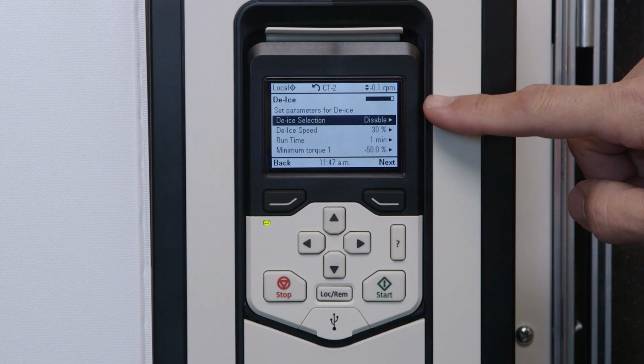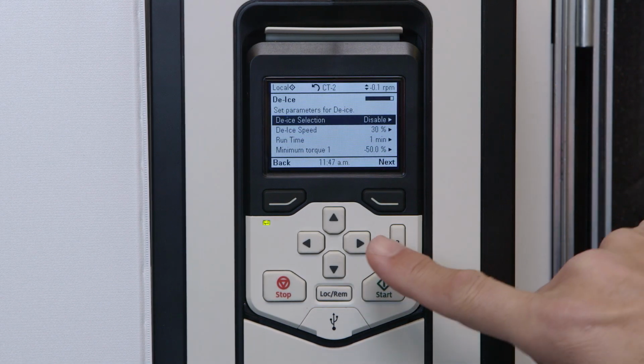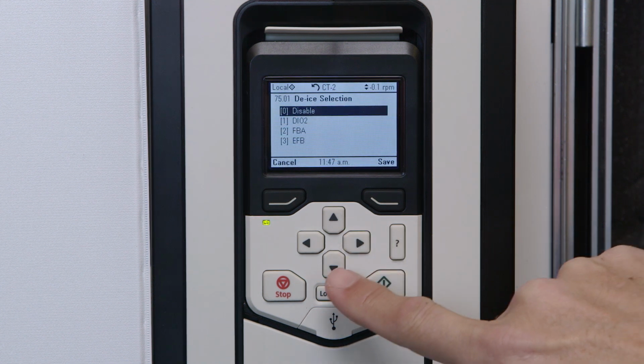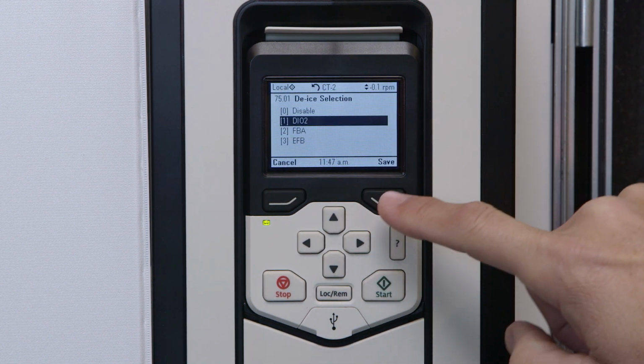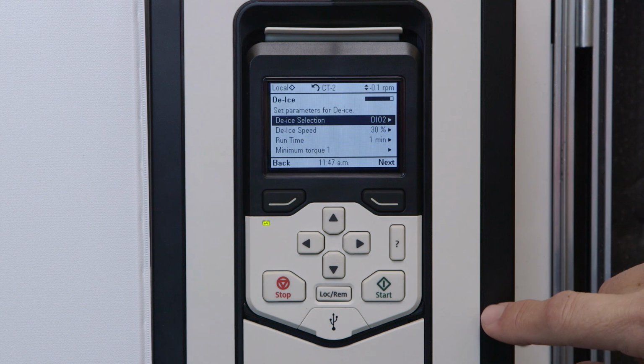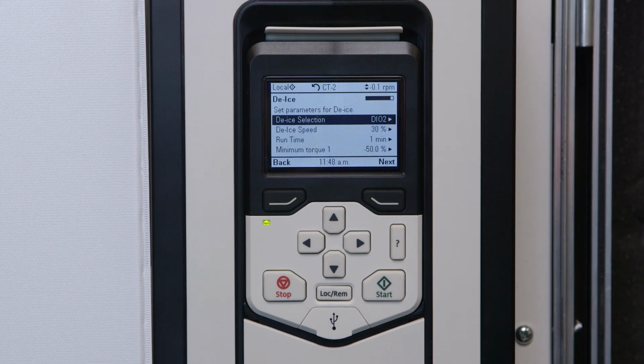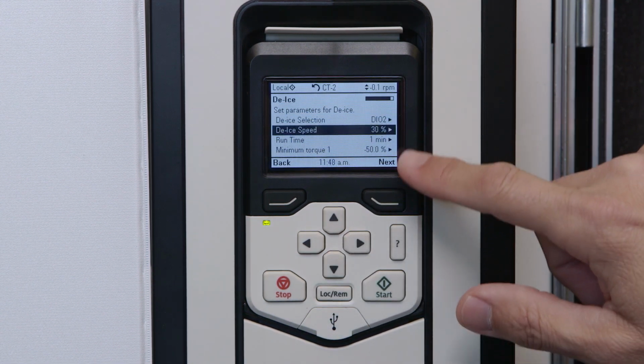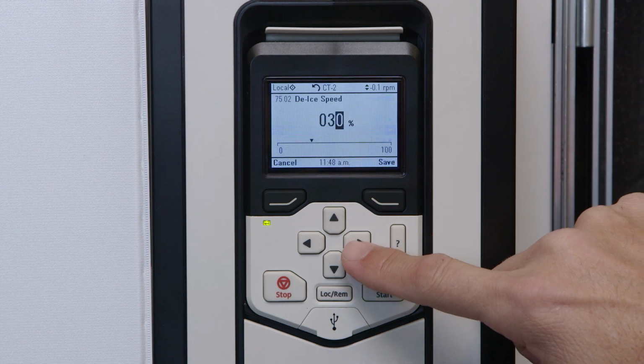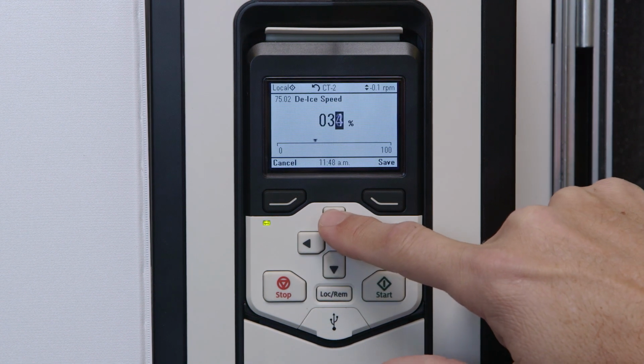If the optional BMS de-icing command is installed, change the de-ice selection field to DIO-2. Then press Save. The de-ice speed and runtime can be adjusted to your preference within the guidelines specified in the O&M.